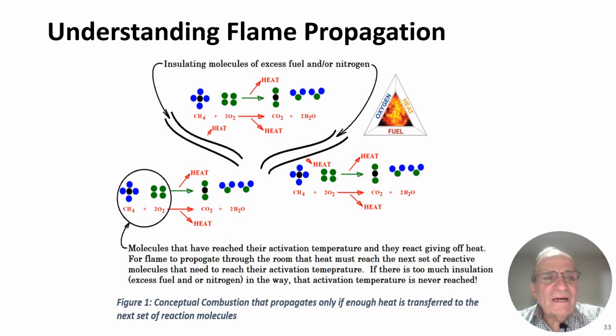Let's talk for a moment about how flame propagates. Now, I can have a room that is filled with, let's say, 3% methane in air. Strike a match, and the match will glow and then extinguish. Why did the room not explode? We'll talk about why. Or I can have a room that's filled with 25% gas and air. And I might have trouble breathing in that because now I've depleted some of the oxygen content of the room. But I strike a match, and again, the flame does not propagate away from the match. It glows and then extinguishes.